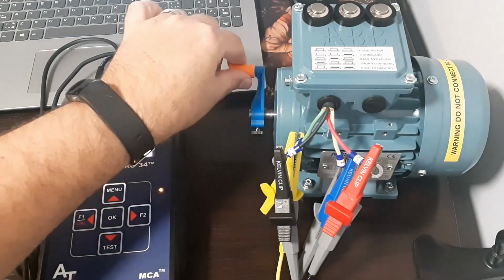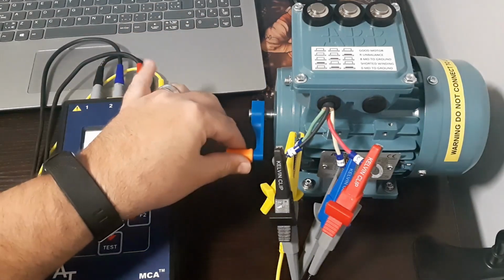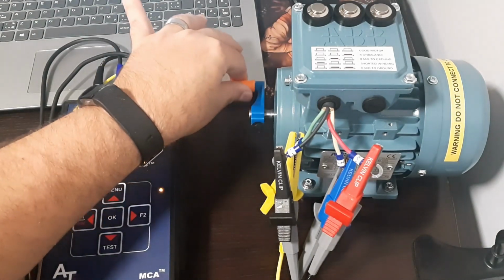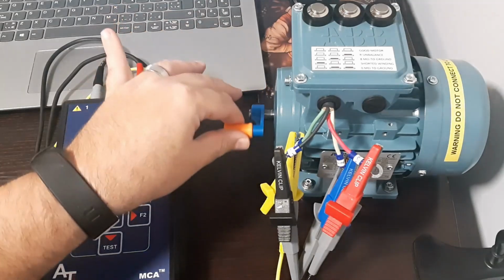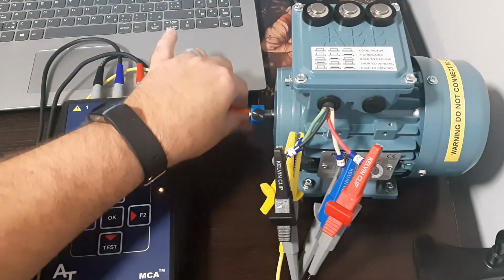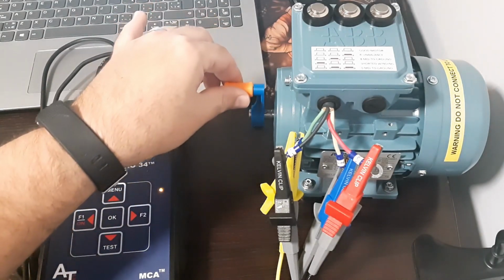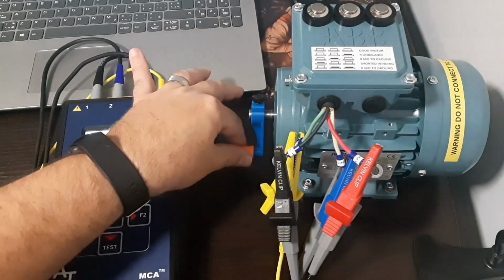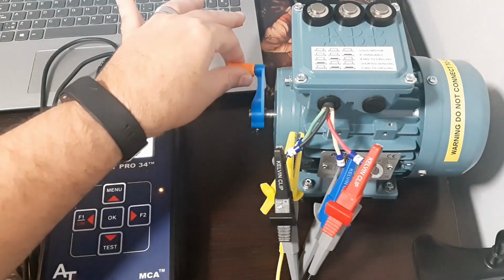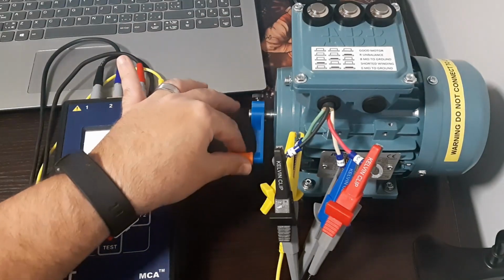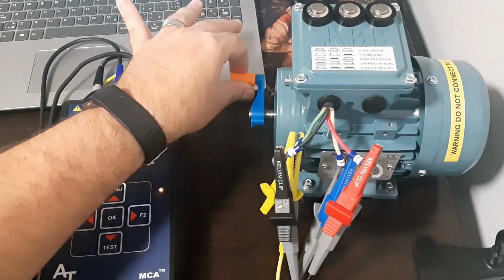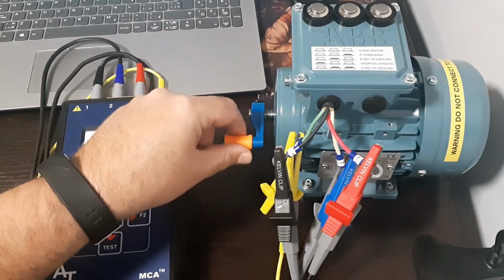Now, it beeps about once every second, so what I'm aiming for is 4 beeps a rotation, which allows me to keep track of this for a nice steady hand on there. If you are jerking it around, you may get some weird readings. So you do want it to be a steady rotation as you're doing it.